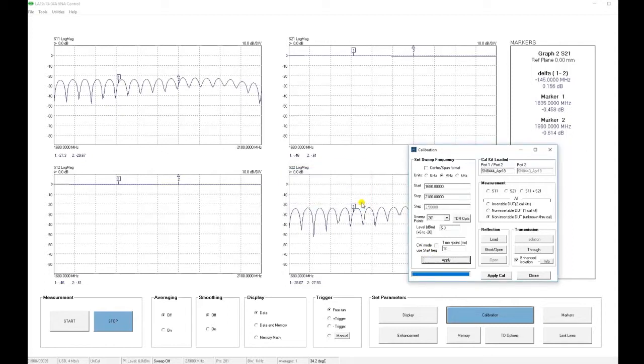For the enhanced isolation calibration to work best, we select the insertable DUT measurement, and we make sure we have this checkbox here ticked. That ensures we use the enhanced isolation calibration technique. At the moment, I have the measurement bandwidth set to 1 kHz, so the first step that we can carry out is the through calibration step.